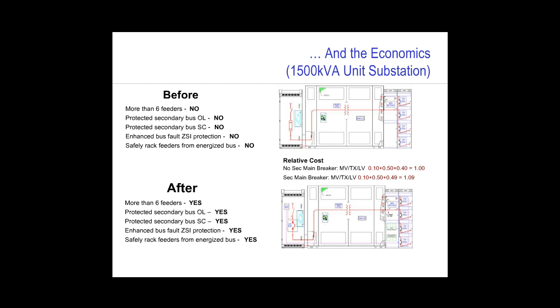If I add a secondary main breaker to this assembly, and I would recommend that we do this today whether we use the new designs or not, there is an incremental cost. Adding that breaker brings us up to a total of about 1.09, or perhaps 9% higher, with an added cost in the low voltage switchgear. Depending on the rating, you may also add to the footprint of this assembly. In my example, at 2000 amp bus, it's not necessary to add another vertical section.